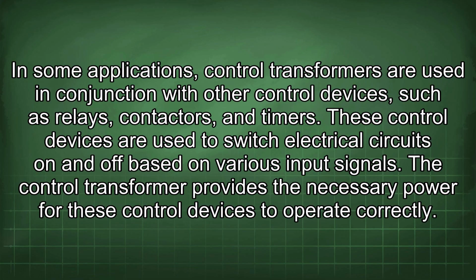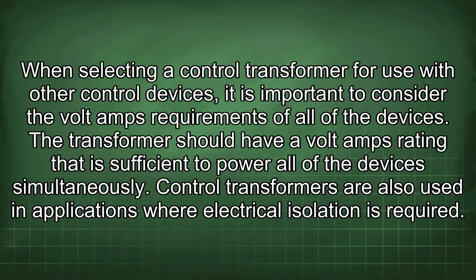These control devices are used to switch electrical circuits on and off based on various input signals. The control transformer provides the necessary power for these control devices to operate correctly. When selecting a control transformer for use with other control devices, it is important to consider the voltamps requirements of all of the devices.